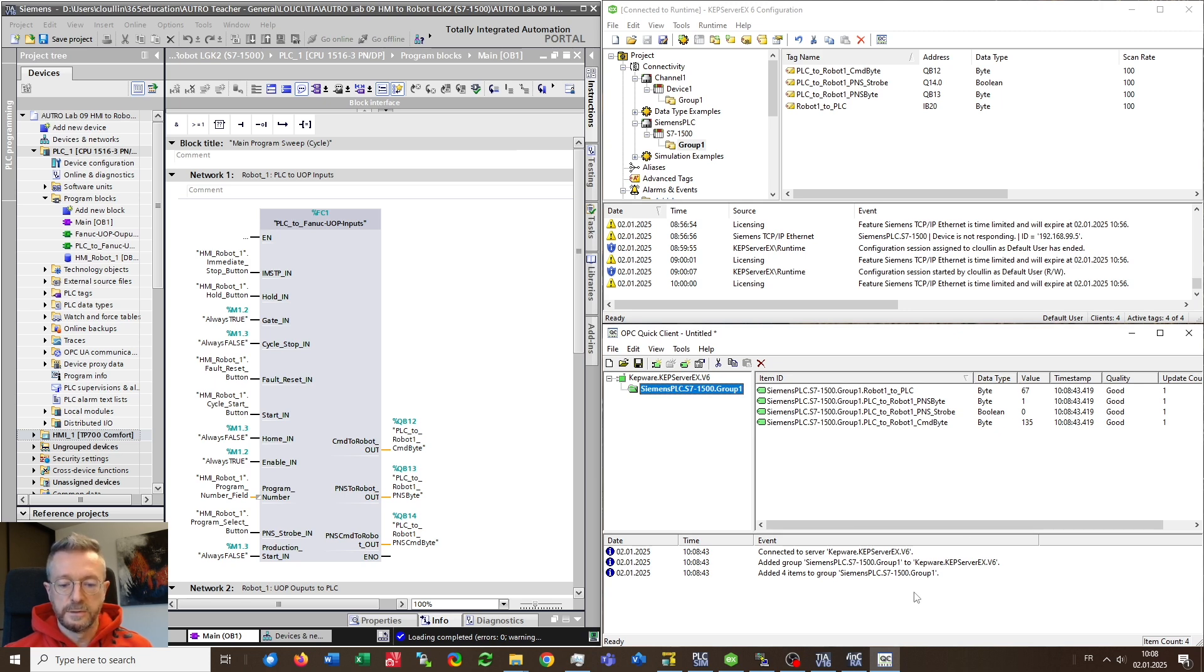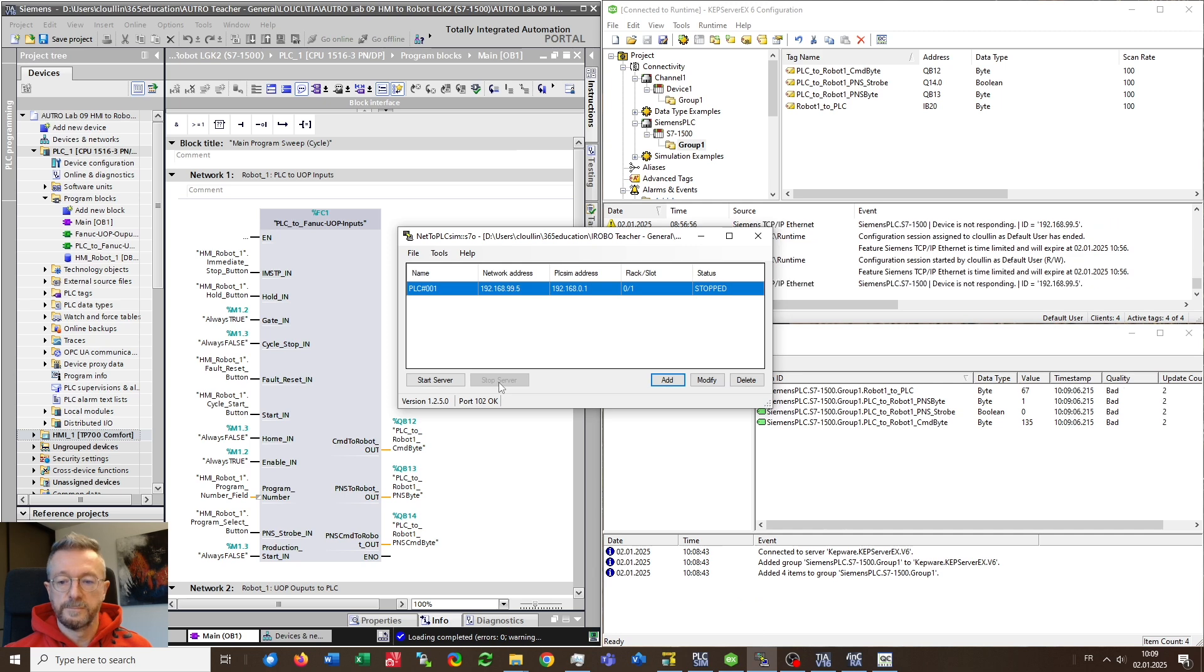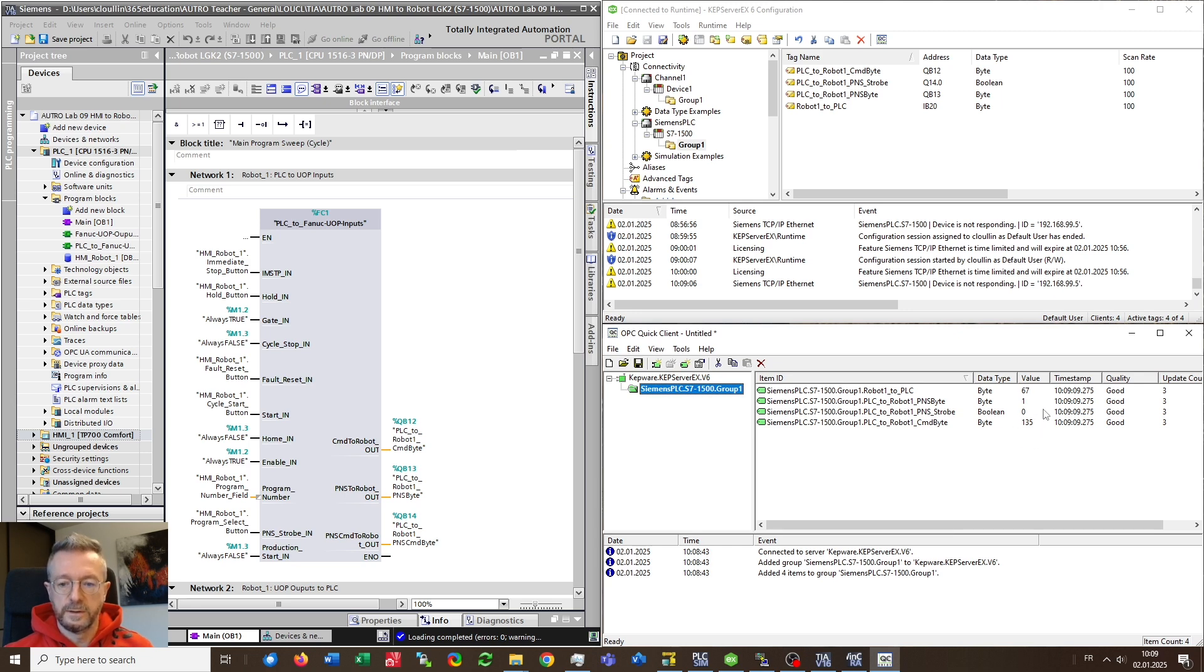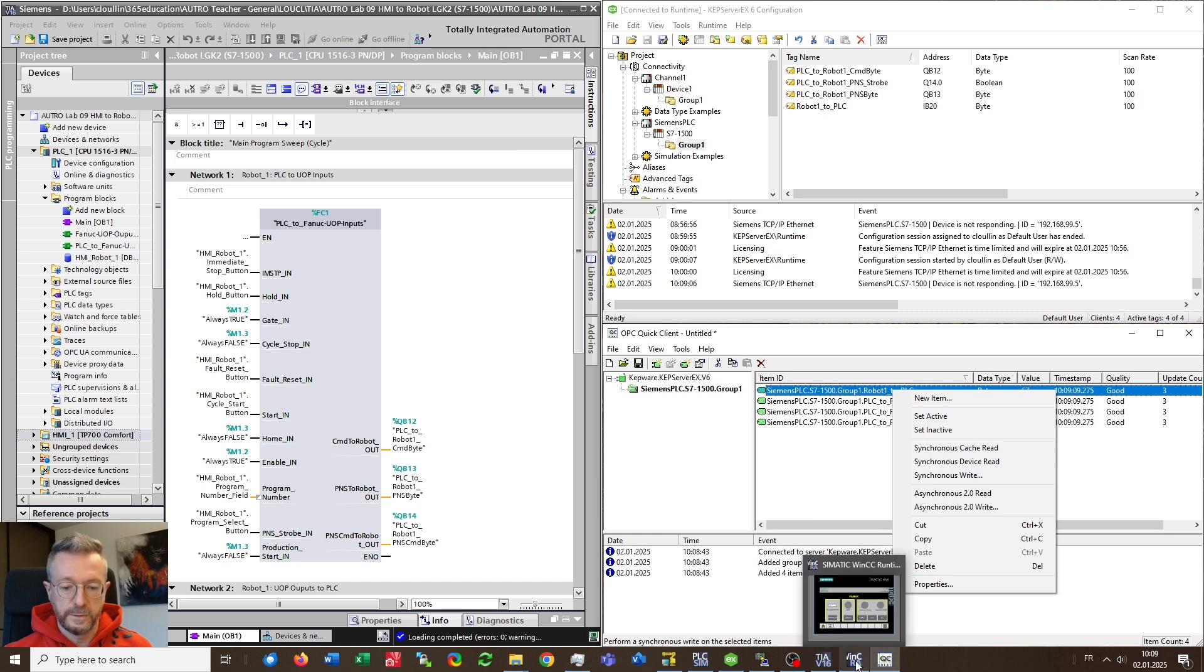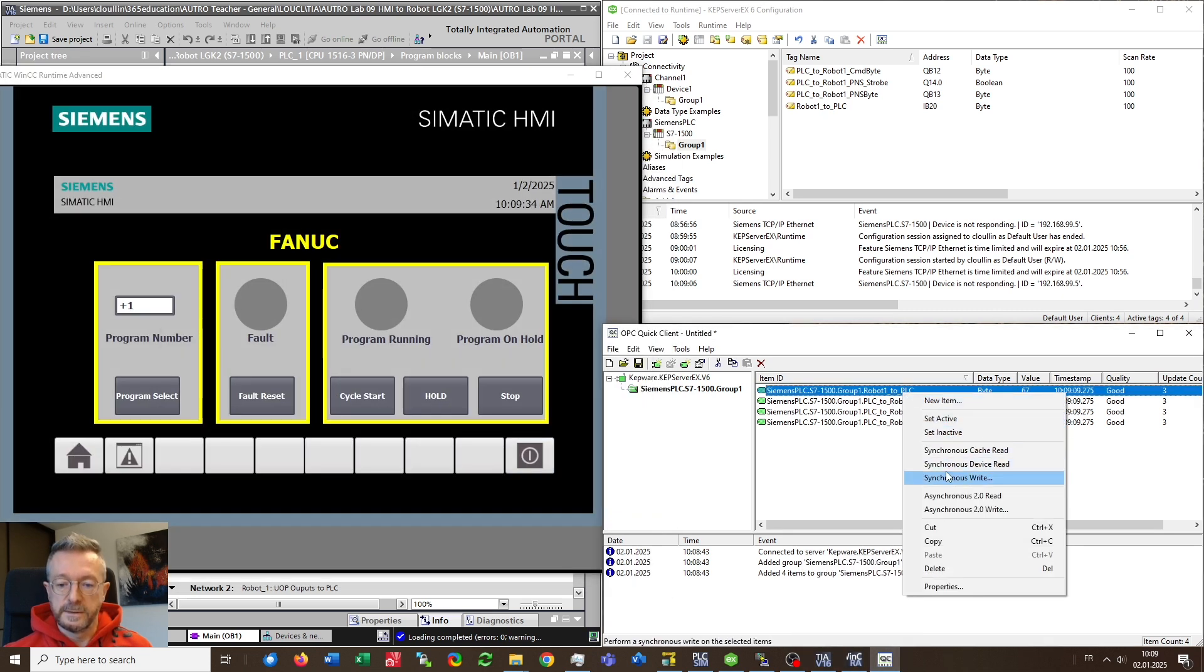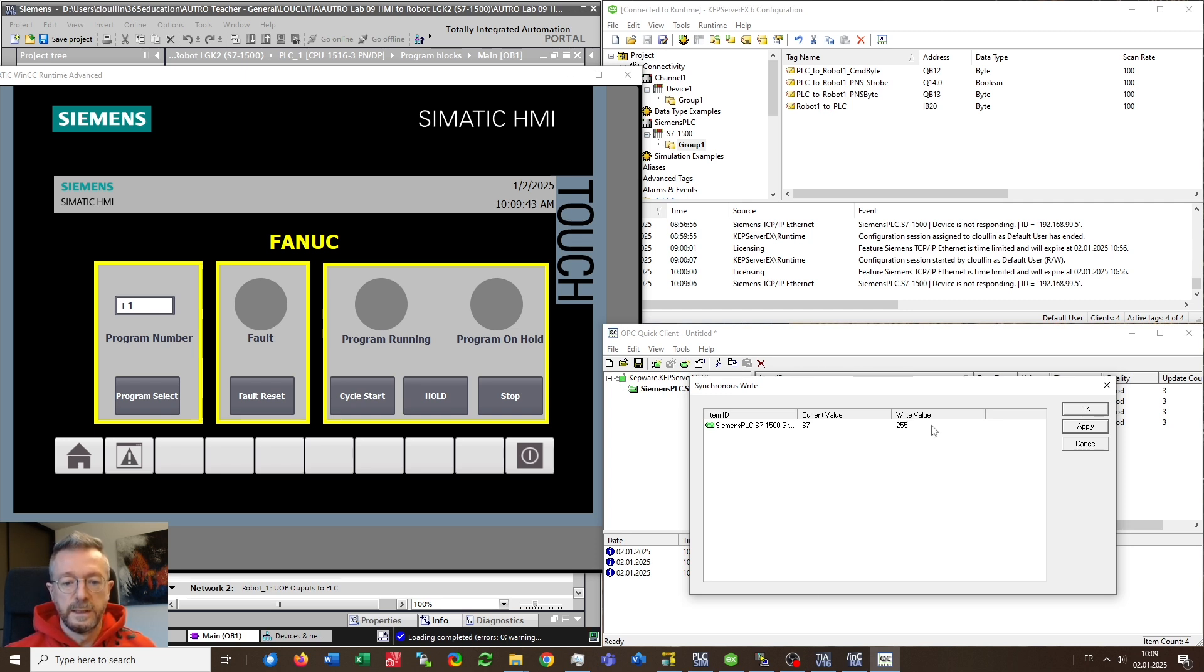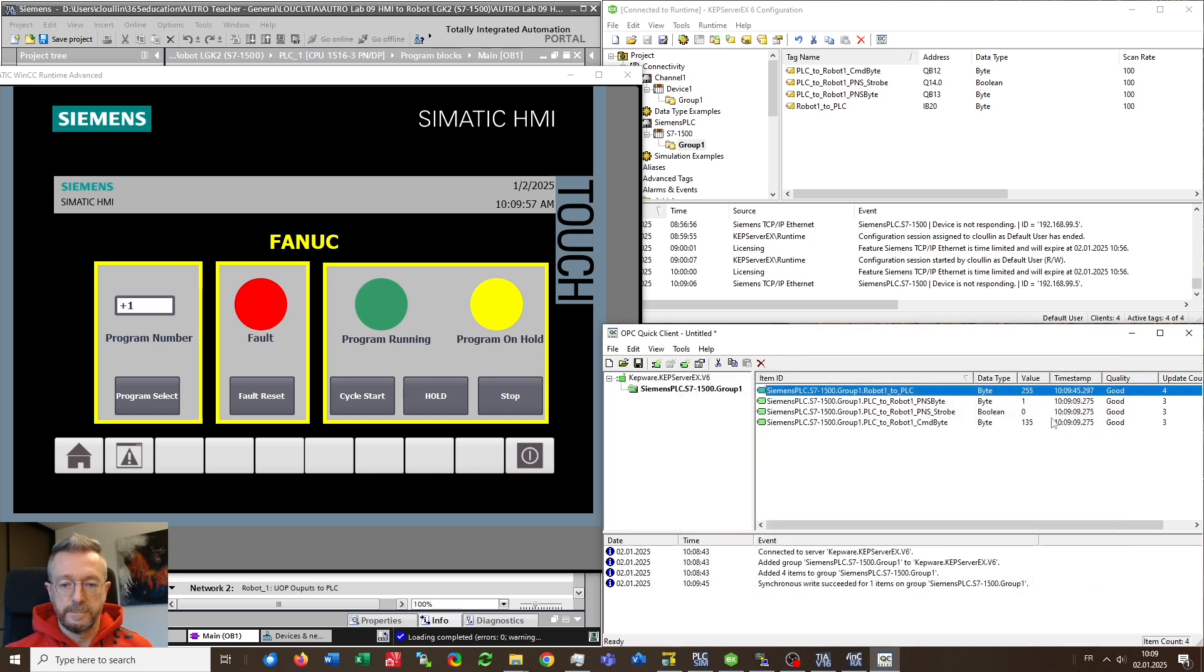So if something in the chain before is not correct so this will instantly change to bad for example if I stop the NetToPLCSim server this gets bad. If I started again everything is up and running. So what we could do here is we can read already the information that is sent from PLCSIM to KEPServerEX and we have also the return information that we can modify here. So let's take a look first at our HMI so as this is the status information what I could do just for testing is enter 255 which is putting every bit of this byte to 1 and you see that all the signalization lamps light up.